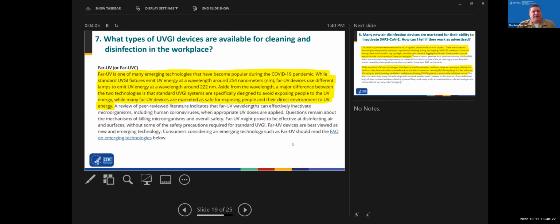The other one I'll touch on, Ken mentioned this as far as an emerging technology, is far UV. It has become very popular during the COVID-19 pandemic. The 2 systems that I told you about previously use UV energy at 254 nanometers. Far UV is a shorter wavelength, down around 222. It appears that it is safer for people than we once thought, and it appears that it can be effective at inactivating microorganisms as well. This is probably the emerging technology that is further down the path to mainstream acceptance, but CDC is not to that point yet. So just be aware that it's out there. If you use it, there's some homework that you need to do to make sure you're convinced that it's going to meet the needs that you have.